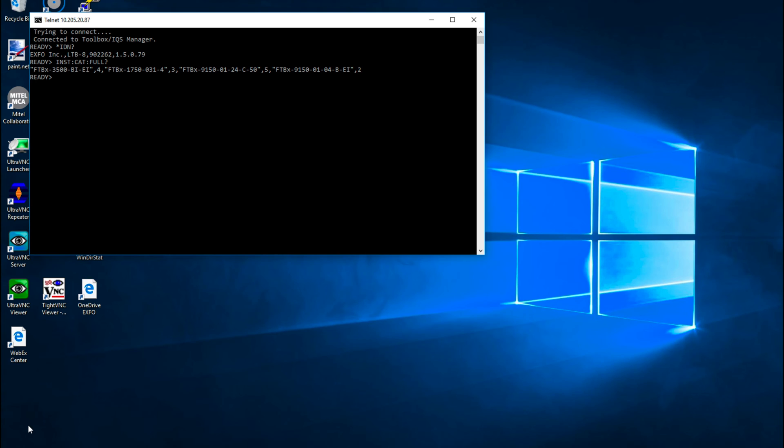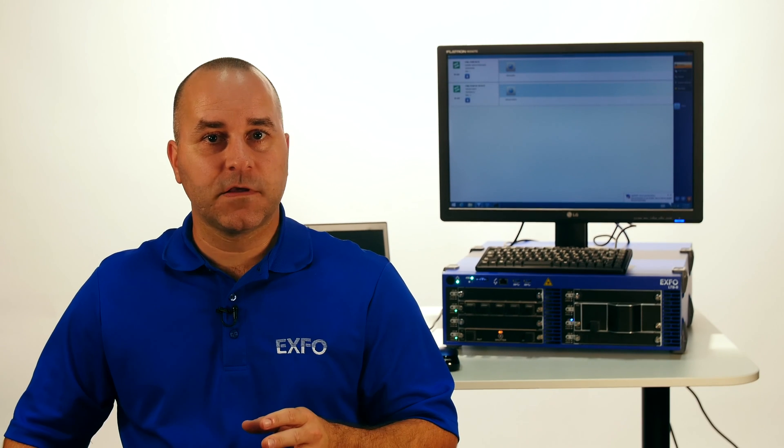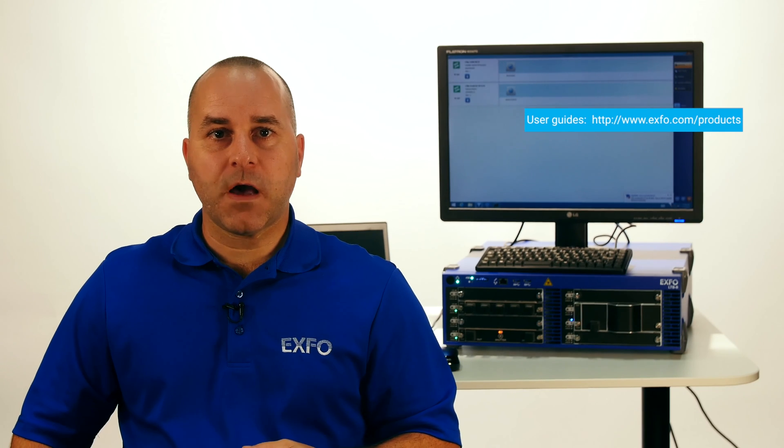For example, setting this command will ask the status of the logical instrument at address 3, in this case a power meter. Please note that every module command will need to be prefixed with LINS X, where X stands for the logical instrument number targeted by the command. The list of SCPI commands specific to a module is available in a dedicated section of each module user guide. Please consult exfo.com under products menu for the details.